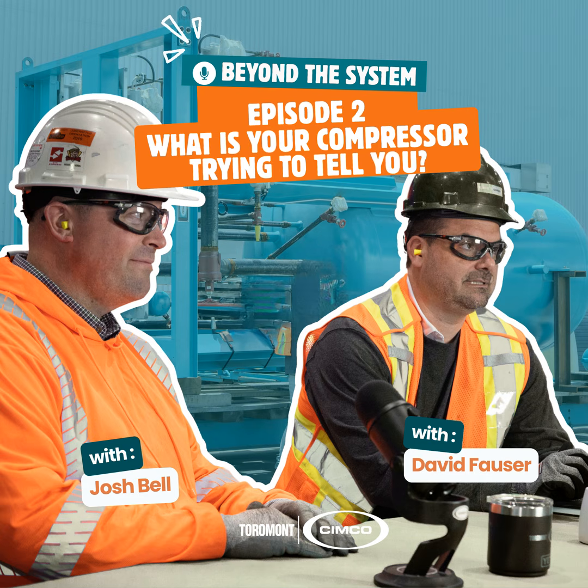So you're going to want to make sure you get your jacket cooling temperature. And that's if it's an ammonia compressor. The odd R22 older system with reciprocating machines out there in the world will also have jacket cooling. But typically on the Freon systems, the temperature under the heads doesn't get high enough to require it. So your jacket cooling temperature, your high pressure, your oil pressure, and your low pressure are typically all the things you're going to want to record.